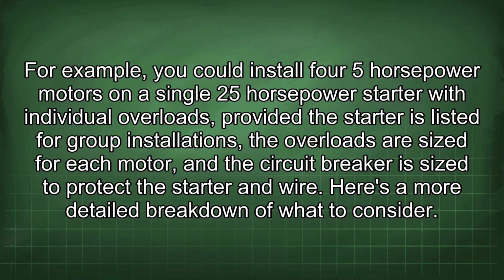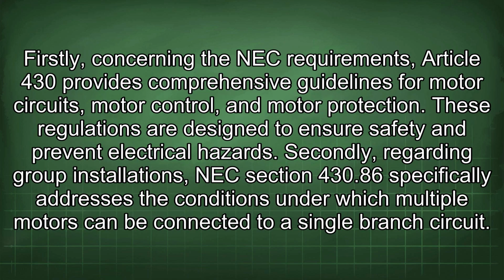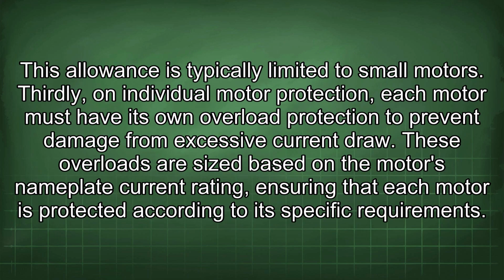Here's a more detailed breakdown of what to consider. Firstly, concerning the NEC requirements, Article 430 provides comprehensive guidelines for motor circuits, motor control, and motor protection. These regulations are designed to ensure safety and prevent electrical hazards. Secondly, regarding group installations, NEC Section 430.86 specifically addresses the conditions under which multiple motors can be connected to a single branch circuit. This allowance is typically limited to small motors. Thirdly, on individual motor protection, each motor must have its own overload protection to prevent damage from excessive current draw.